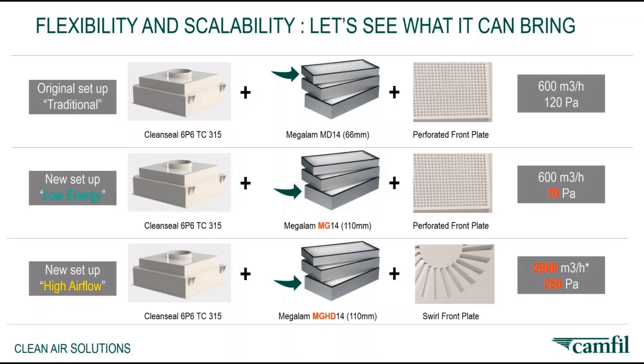Finally, another possibility is to increase airflow by X%, to upgrade, for example, the room from ISO 8 to ISO 7. The same housing, another filter 110 millimeter high airflow, a swirl or 4-way diffuser, and possibility, in theory, to reach 2000 cubic meter per hour with 250 Pascal, remaining H14 efficiency. Of course, pay attention to noise level and pressure drop available with this setup from your air handling unit, but I'm sure you got the point and you will know how to use this flexibility and housing scalability.